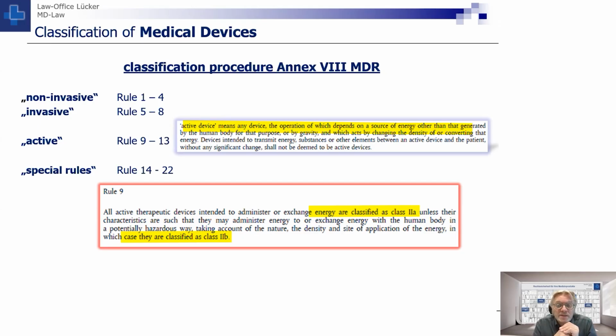So we have that with a treadmill, and which acts by changing the density of or converting that energy. And we just have seen in the demonstration of Björn quite clearly exactly that changing of the density, or better said, the converting of that energy by the belt to the specific subject. So each treadmill, if it's a medical device with a medical purpose, is directly seen as an active medical device. Rules 9 to 13 apply. You can see by the first sentence of Rule 9 that, at the end of the day, a classification as Class 2 is obligatory. There is no possibility less than Class 2. Whether it's Class 2A or Class 2B might be decided by that sentence, but under Class 2, there's no way out.